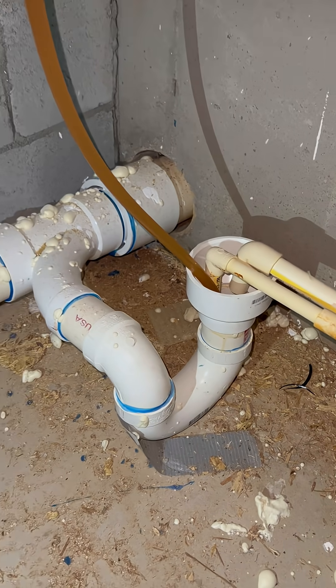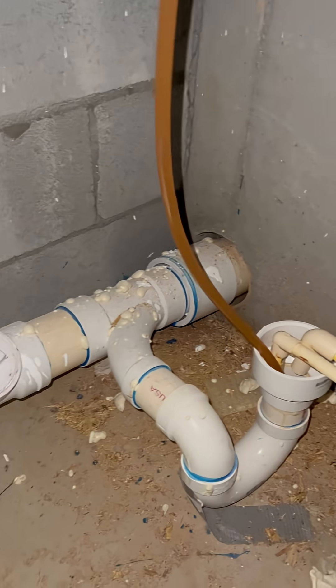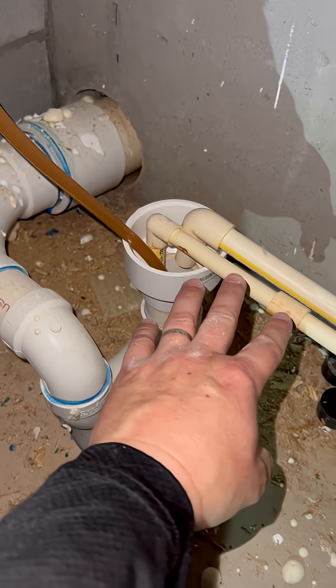Another little tidbit from a crawl space. We've got the main sewer line going out that way, carrying all the solid waste and other waste products. We've tapped into it right here for a couple of condensate drains — a couple from the water heater, which is right here, and which is a full sealed combustion unit. You want two PVC pipes on the top of that.